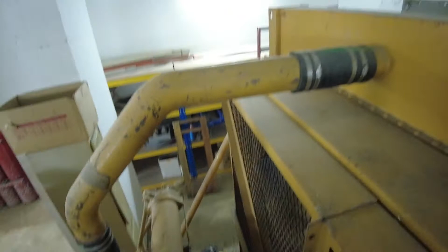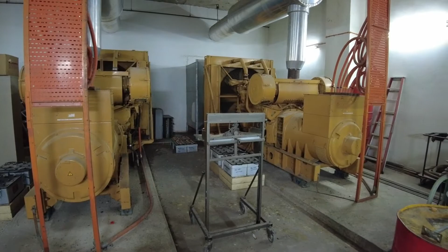Yeah, the floor is a bit dirty to be cleaned up. Okay, no obstruction on the emergency fuse or the night lever. Make sure ACB is on. Okay, close. Okay, we are going to test run the genset by simulating a signal from the UVR relay. Now let's go to the LV room.